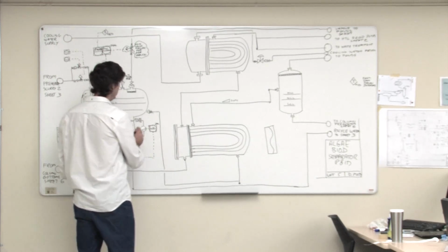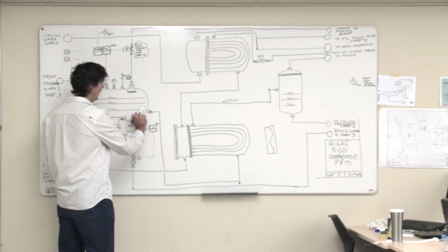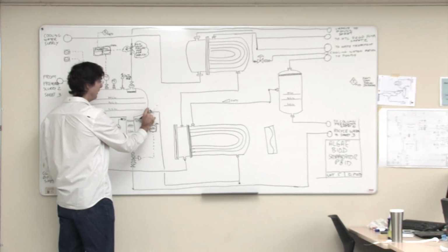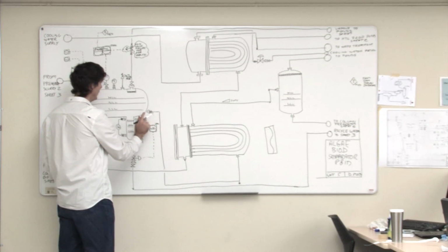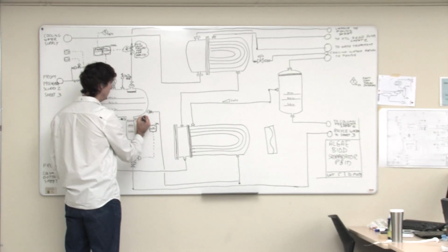Now one thing is, I want to know that the level is getting close to that nozzle. And if I put the bottom level transmitter above it, then I'll never actually know. So I need to put the bottom level transmitter down here, down below the outlet of the oil. So I'm going to put a nozzle on here.